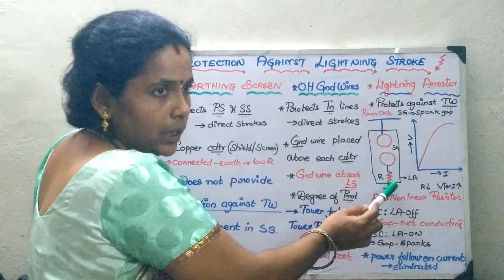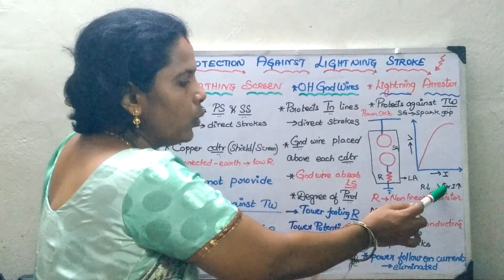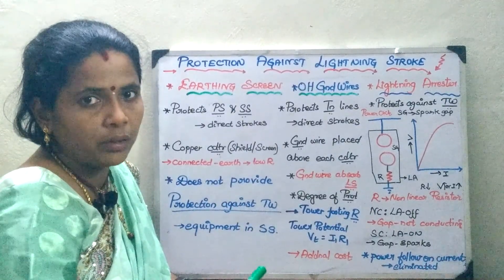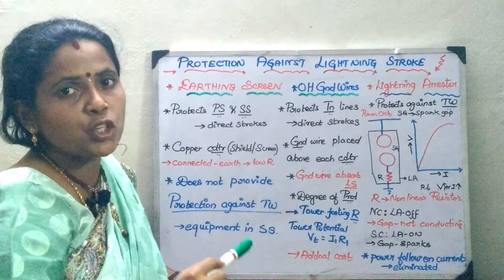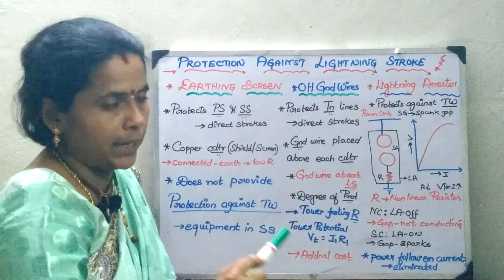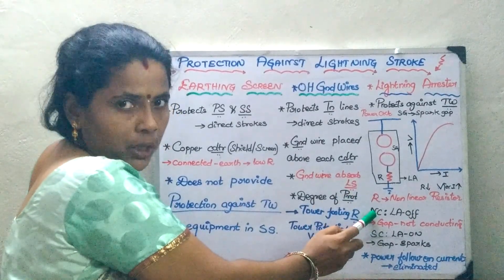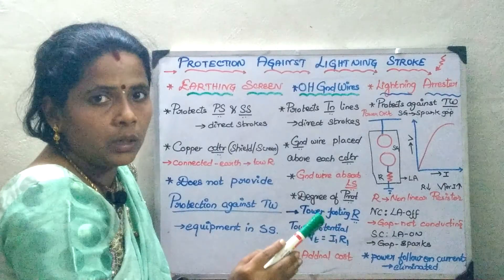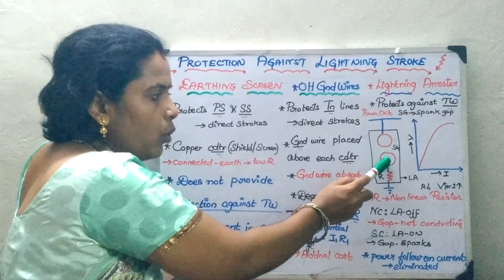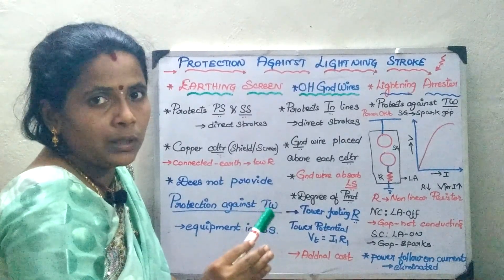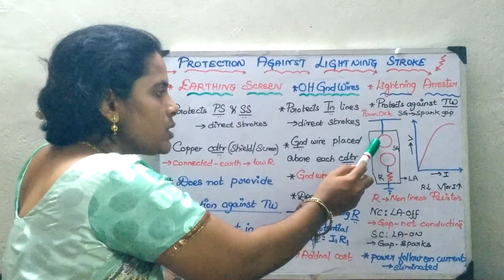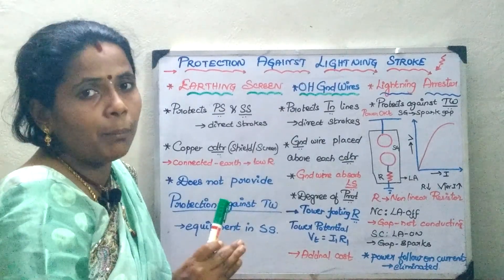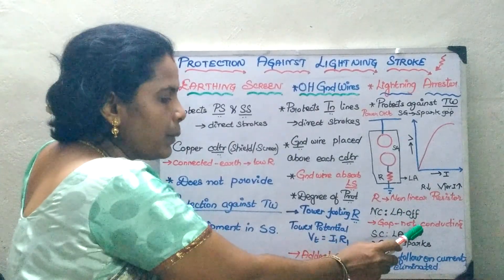The non-linear property of the resistor is used for the working of your lightning arrester. This resistor offers low resistance when the voltage or the current gets increased. Under normal condition, the lightning arrester should not conduct — it should conduct only when there is an overvoltage. Under normal condition the normal voltage should not be sufficient enough to cause the spark over of the gap and drain current to the ground, so the lightning arrester should be in off condition and the spark gap is not conducting.